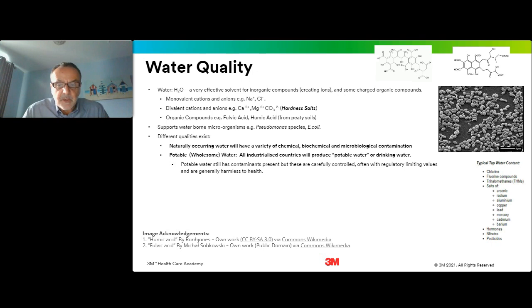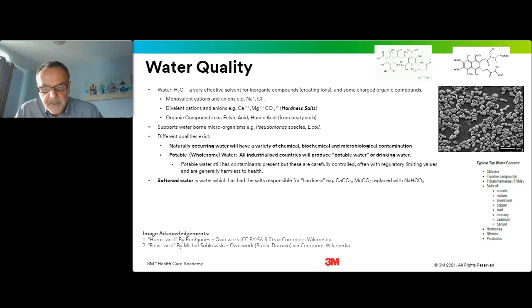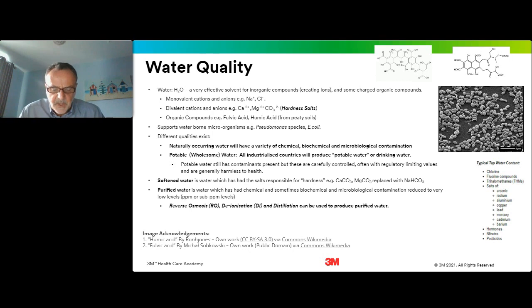So when we come to means by which water can be purified, generally one of the simplest methods is called softening. And this means the removal of the divalent cations responsible for water hardness. In this process, calcium and magnesium cations are exchanged for sodium. So other contaminants will be largely unaffected by this process. Then there are the more involved purification methods, which involve the use of reverse osmosis type processes, deionization, and distillation. And of course, these processes will remove contamination to very low levels.